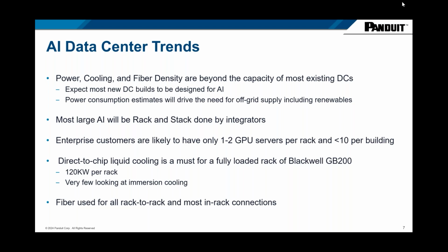So things like direct to the chip need to be in place, need to be incorporated, because the kWs per rack, which is mind-boggling to me, are legitimately hitting 120 kW per rack. For those who've been in the business a while, remember 150 watts per square foot, 300 watts per square foot - those days are long gone. This is 120 kW per cabinet.